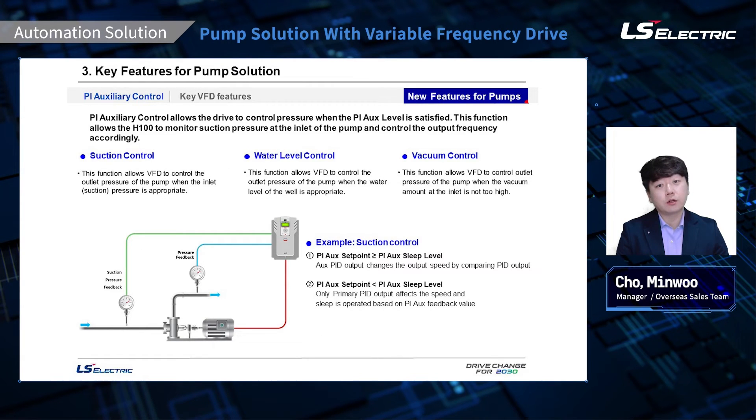In the PI auxiliary control, the primary PID control will be the outlet pressure as long as the PI auxiliary level is satisfied. When the PI auxiliary level is too low — for example, if the suction pressure on the inlet side is too low — the primary control will switch to suction pressure control. Once the PI auxiliary level is satisfied, it will switch back to the PI control on the outlet pressure. PI auxiliary control can also be applied for water level and vacuum level.